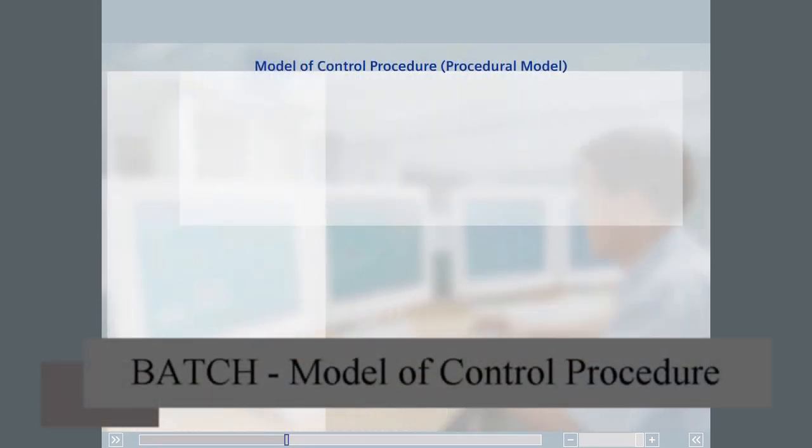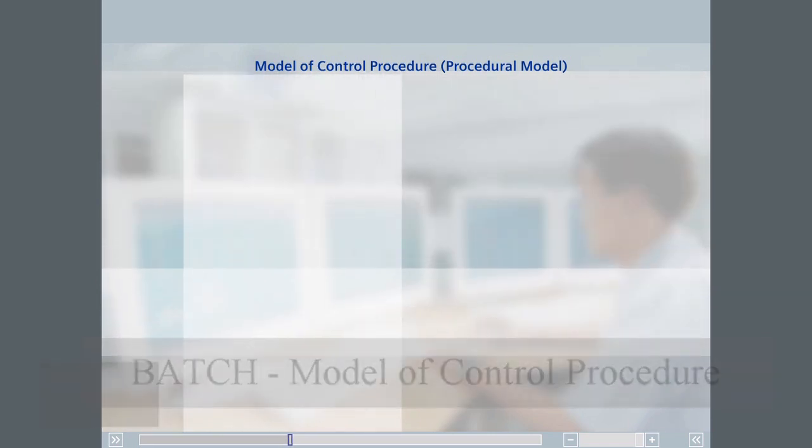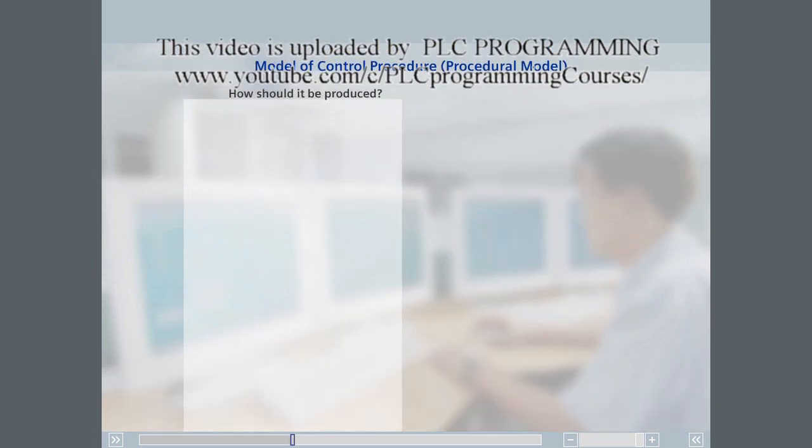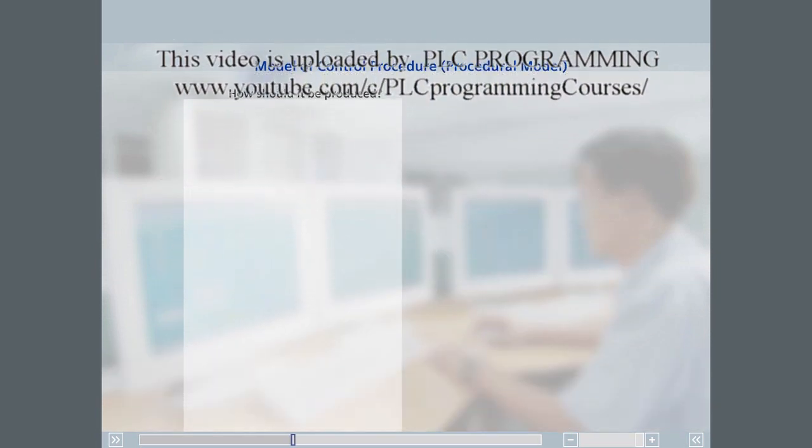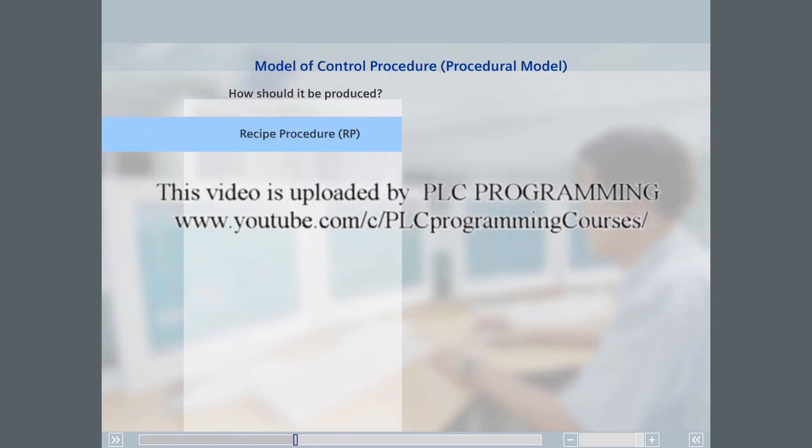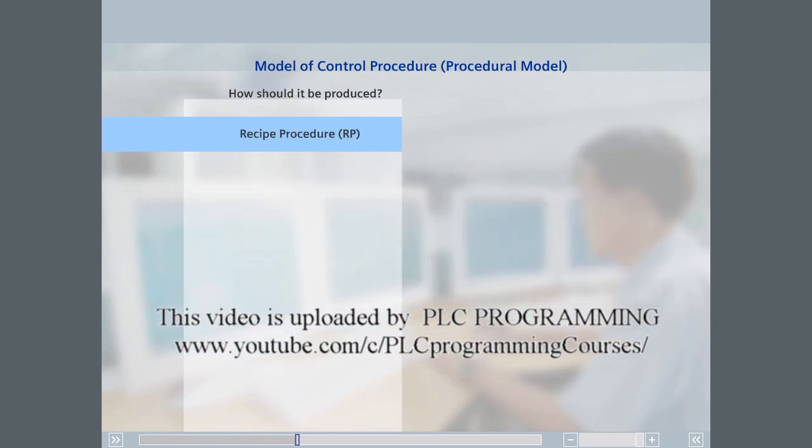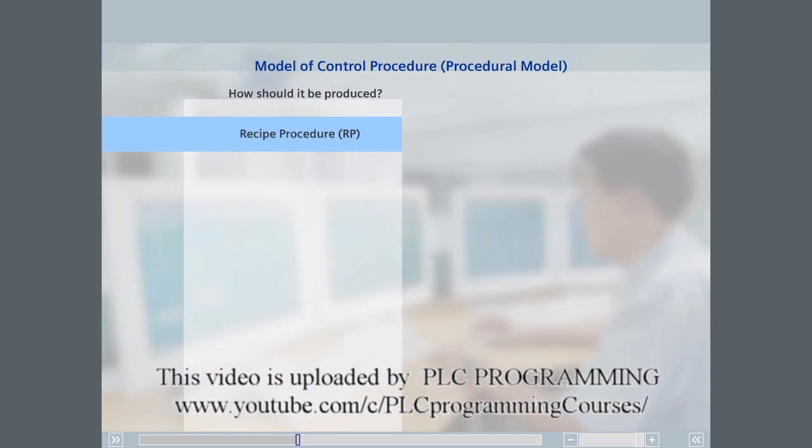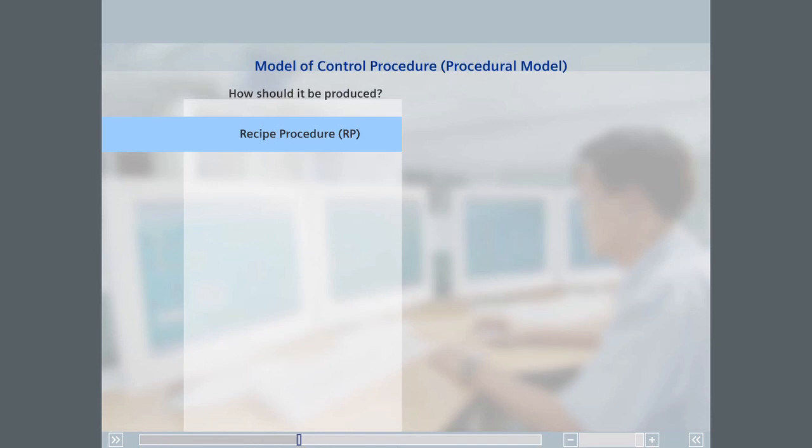The second model of ISA 88 that you will get to know is the procedural model. This hierarchical model allows you to organize the steps needed to produce a product. The top hierarchy level is called the recipe procedure. A recipe procedure runs on a process cell and describes the entire strategy used to produce a batch of a product.